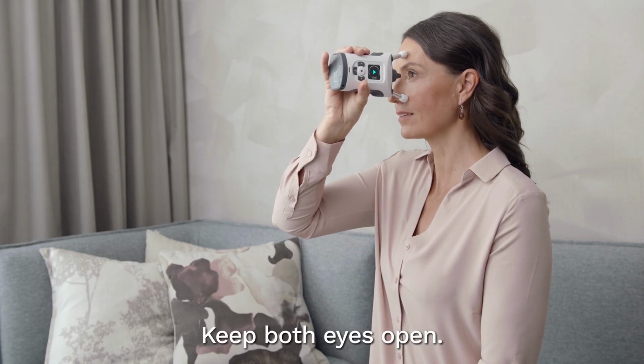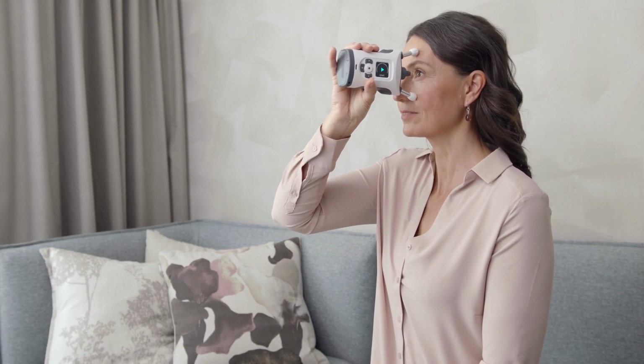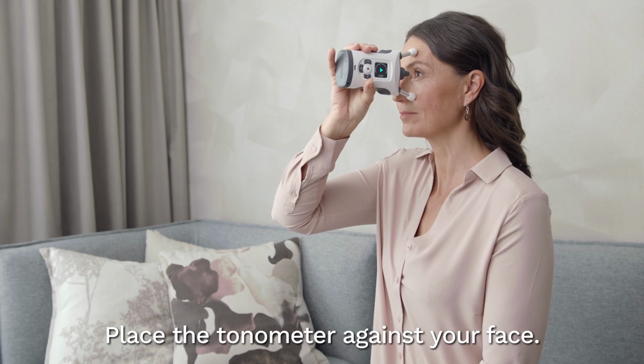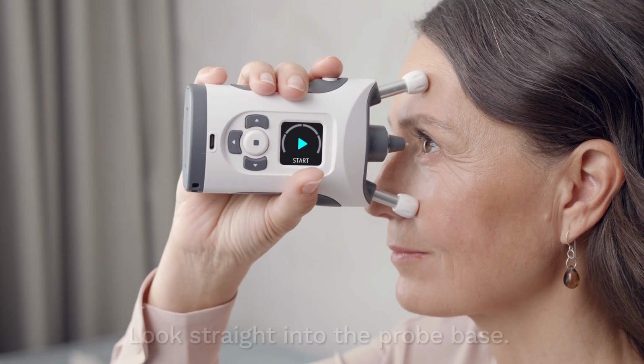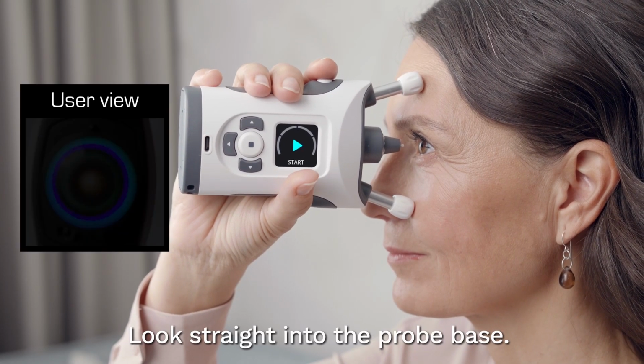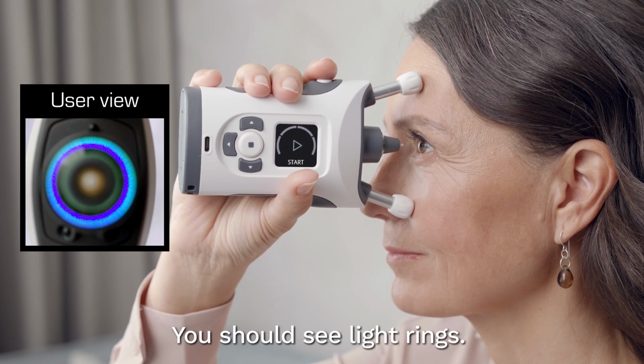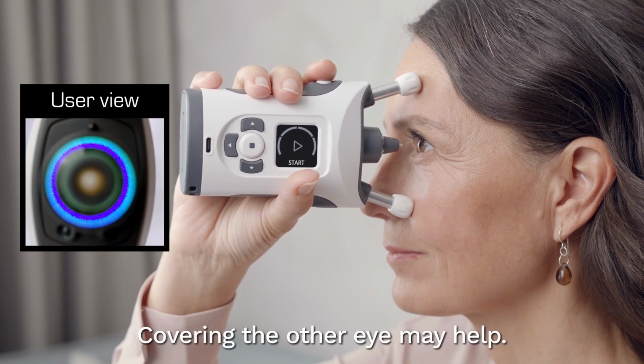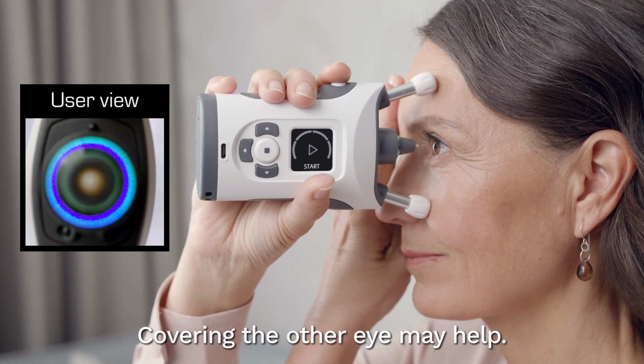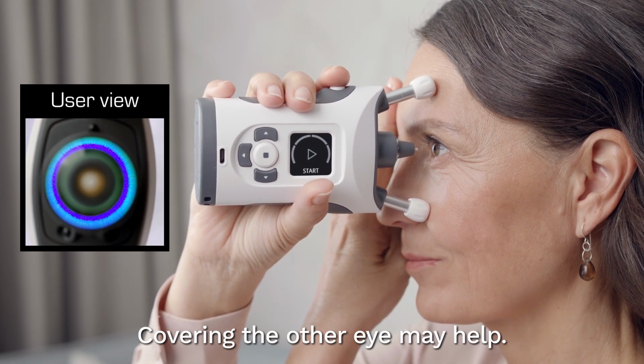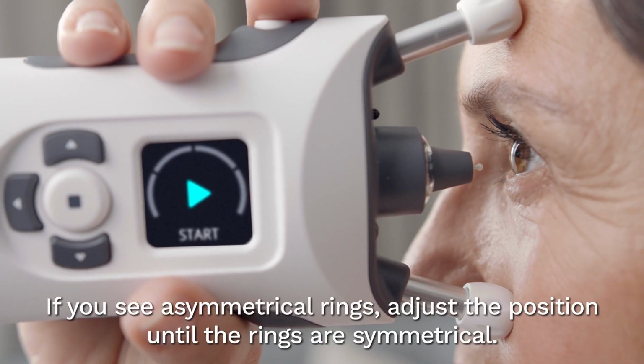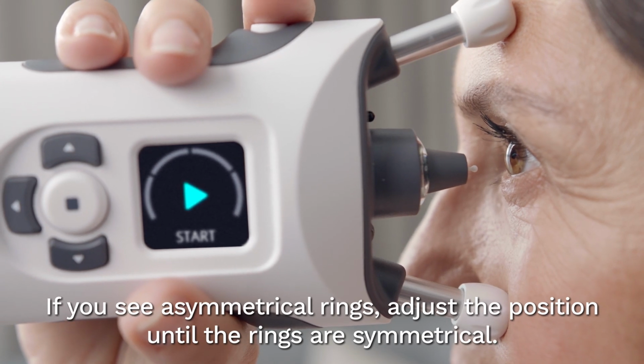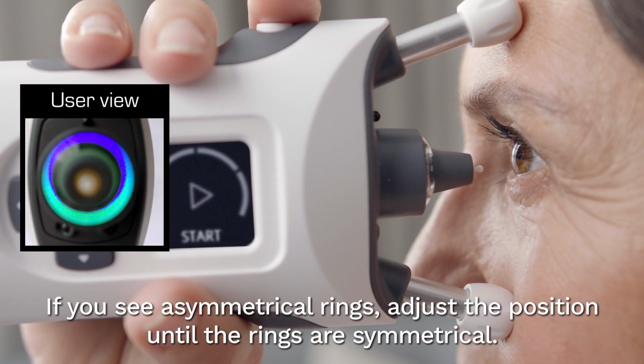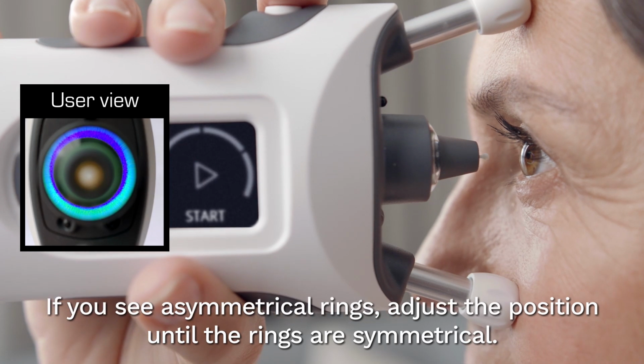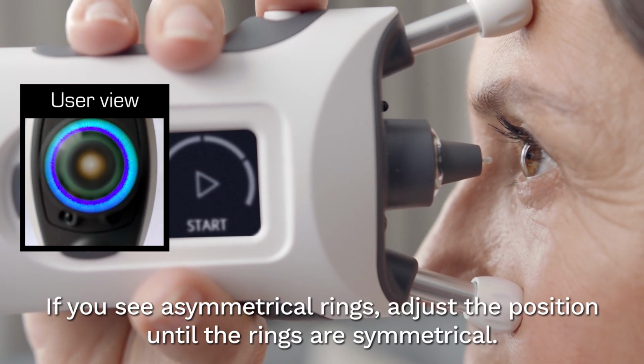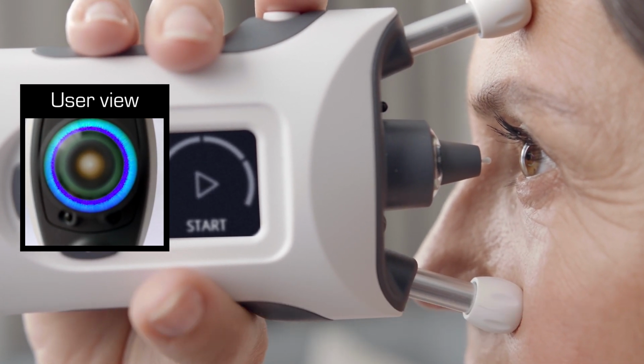Keep both eyes open. Keep a good posture and place the tonometer against your face. Look straight into the probe base. You should see light rings. Covering the eye not being measured may help to see the light rings more clearly. If you see asymmetrical rings, the probe is not centered properly. Slightly adjust the position of the device until the rings are symmetrical.